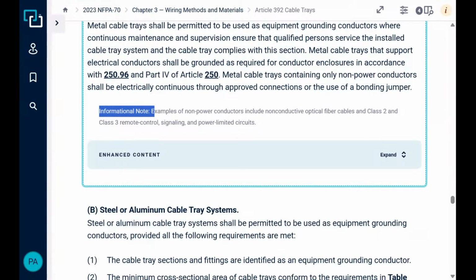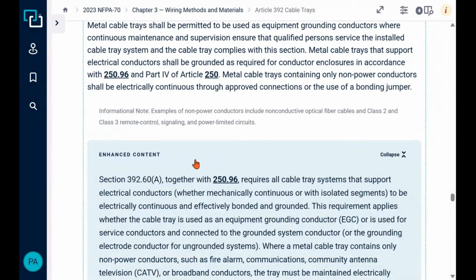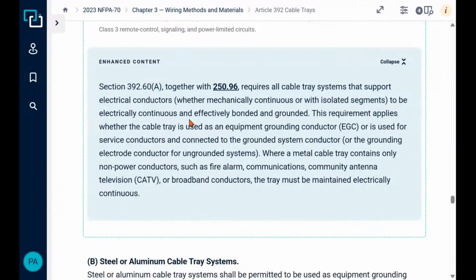In applications where you have non-power, you're thinking, what is that? Well, that's things like class 2, class 3, that's signaling, that would be fiber optics, which all can go in those types of trays. And you also have down here what's called the extra information or enhanced content. So if you're in Link, you have this. If you have the handbook, you have this. This is the blue text. And it gives you that information and some extra commentary.